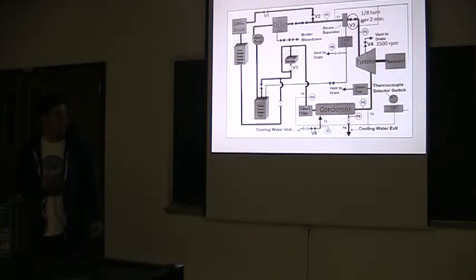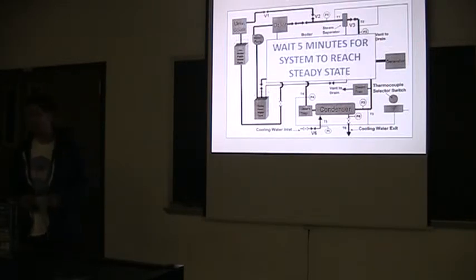For the procedure, first we'll close all the valves. We need all the valves closed except for valve 4. We'll open up V2 and slowly open valve 1 until we get 100 psi on the first pressure gauge. Then we'll slowly start to open V3 until we get the turbine at 1000 RPM for it to warm up. And then we'll open an eighth of a turn every 2 minutes until we get to 3500 RPM. And we'll wait 5 minutes for steady state.